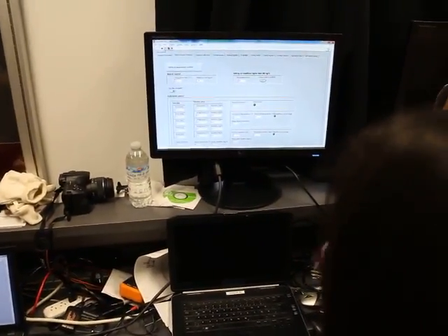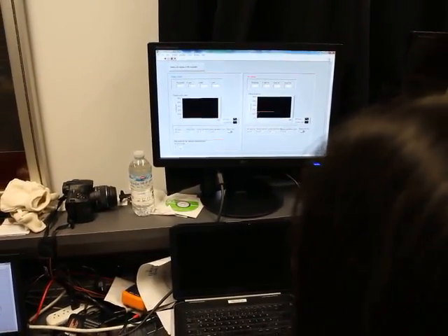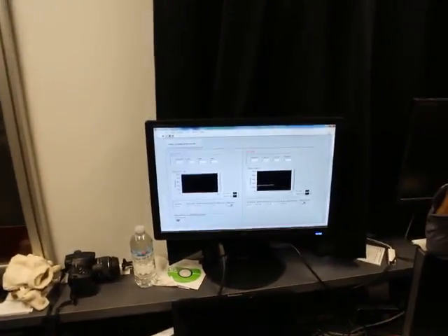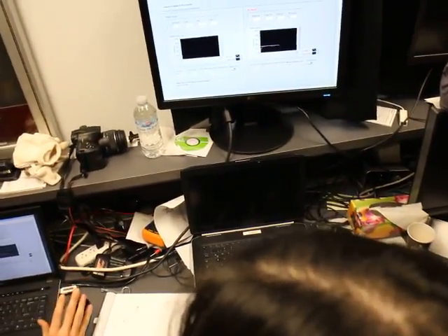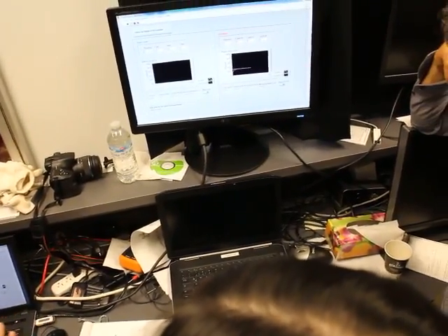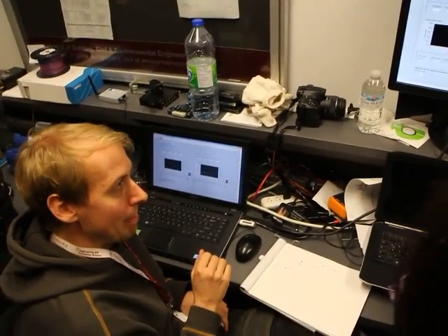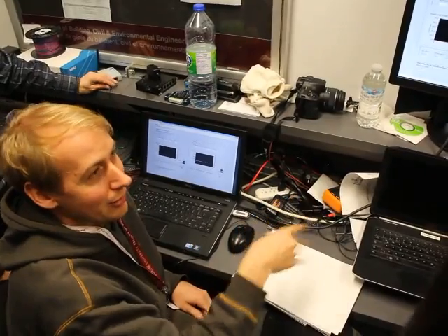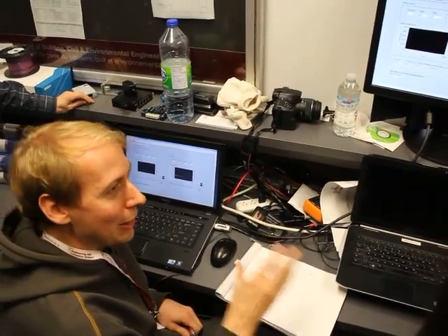So then you have to go to controller. Here's controller. And over here, it is written: only active for air collector measurements. Water mass flow. Here, during air collector measurement, you can set a mass flow for the water to vary the water collector side. That was only set up for the heat exchanger originally, but you are somehow testing a heat exchanger, right? So this is actually what you would do to treat the collector as the heat exchanger in the closed loop air collector test.